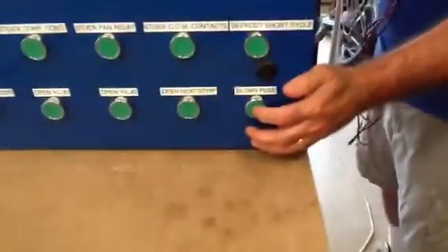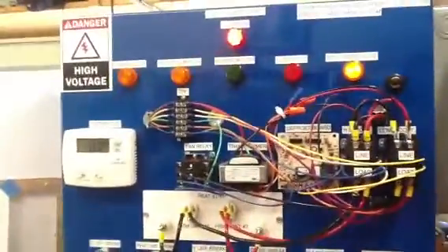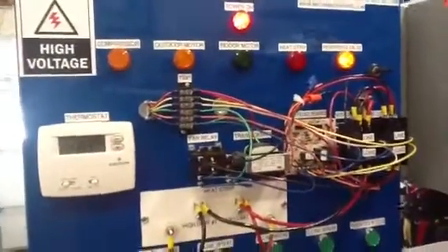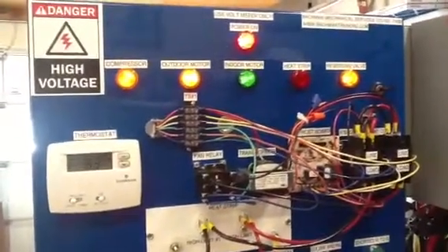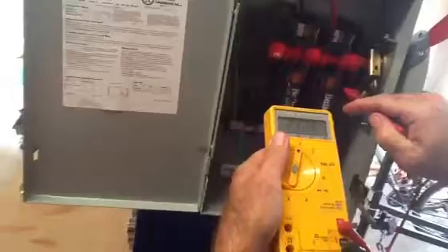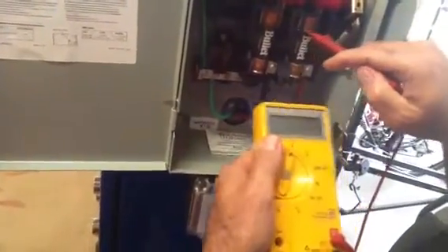So, I am going to push blown fuse, and we should end up in some sort of a function. I think I have a cooling call. There we go. Cooling works. And come back over to the disconnect, and you can see line side 232, load side 233. Obviously, go across the fuses, you should get 0 voltage. So that blown fuse has now magically been repaired by the simple push of a button. That is just one problem that my trainers can do.